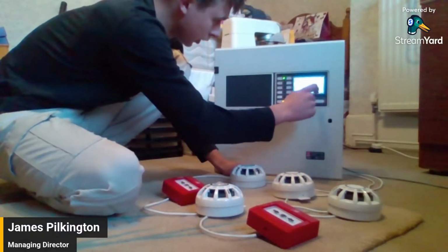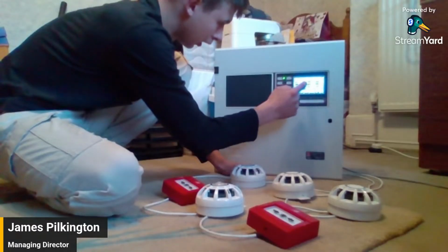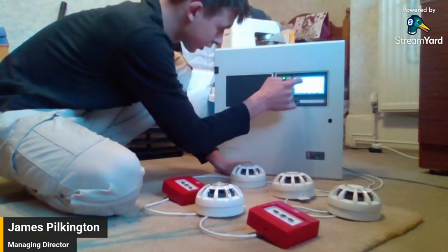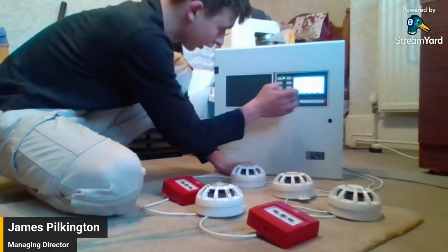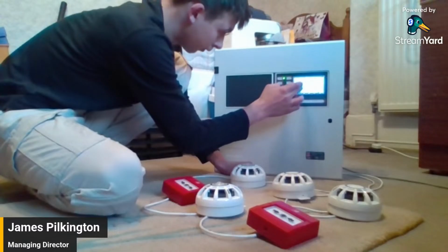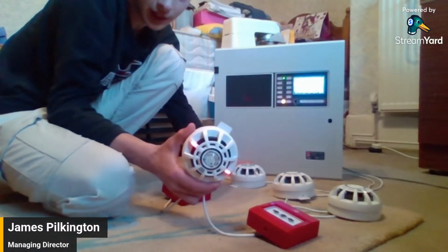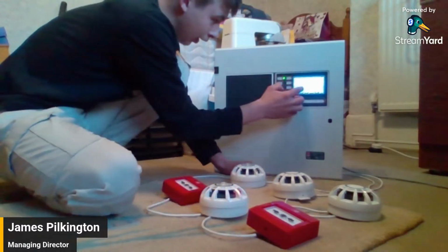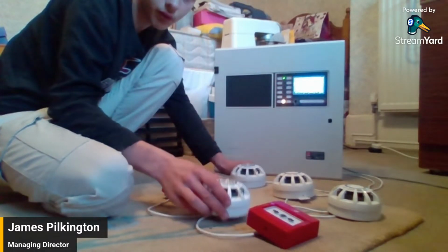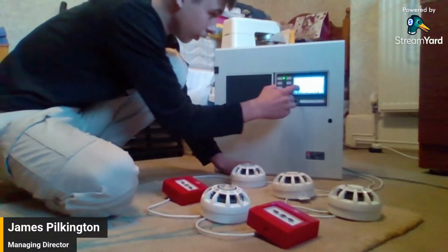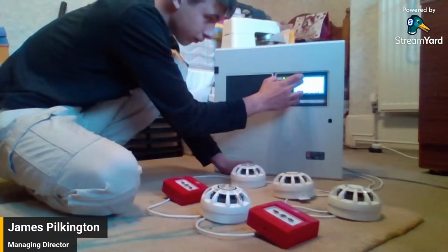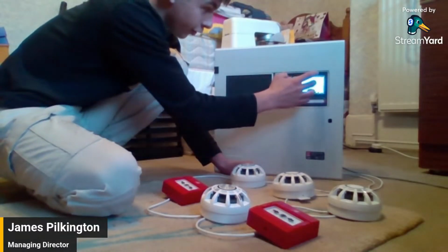So once they're all learnt, come out of the menu and go into Device Manager, and then say I need to find device 3. Click on it, go into device outputs, and you can turn on the fire LED, and I can see this device has lit up. I can turn the beacon on, or I can turn the sounder on, and you can also do that on the alert tone.